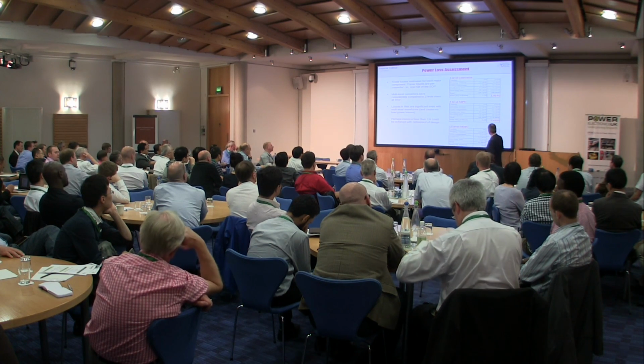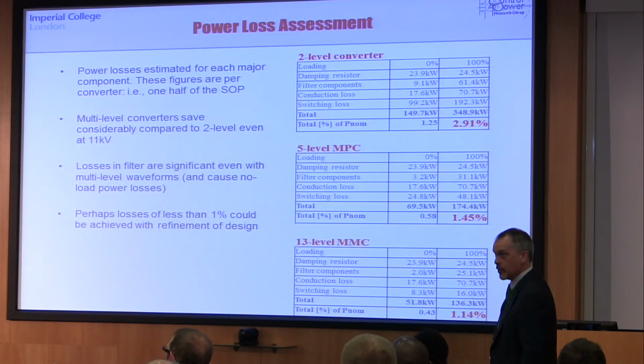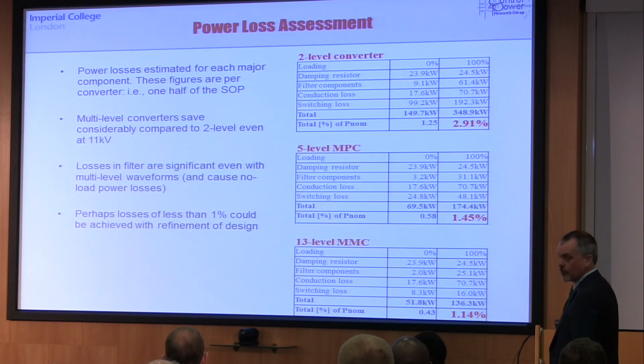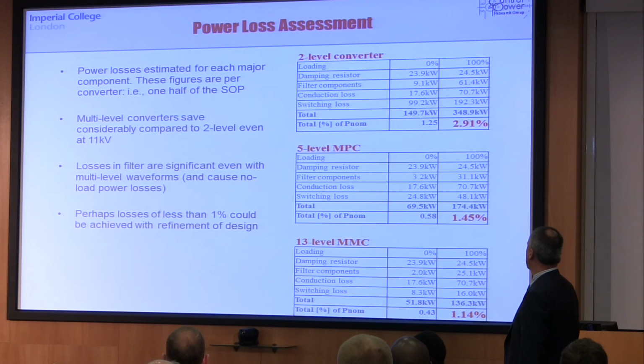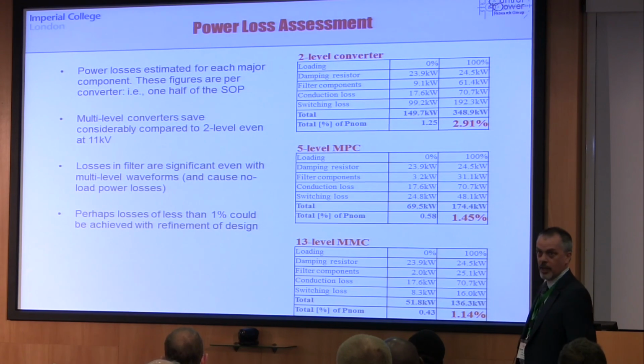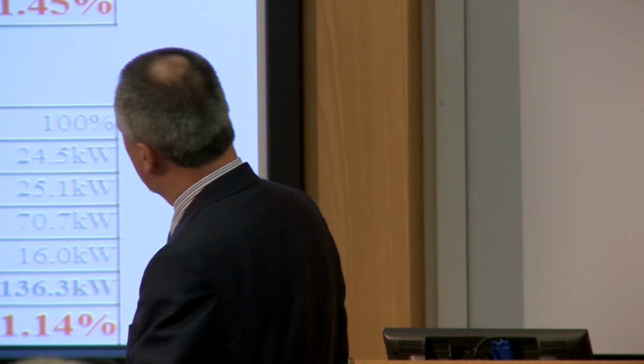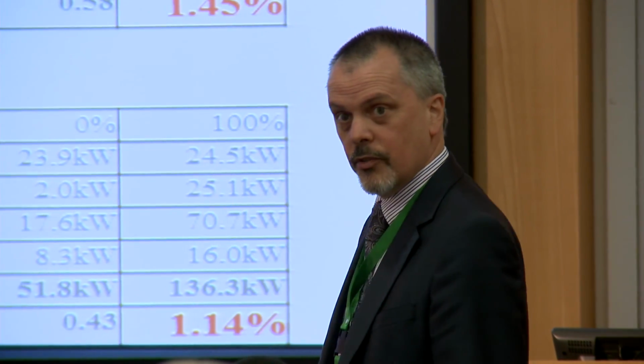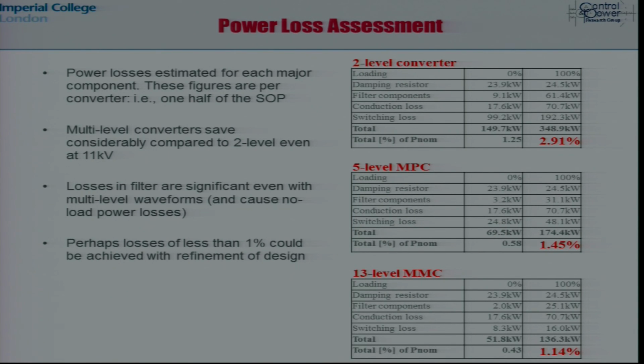In terms of losses, and this is probably where the numbers would get better if we redid the study, going from almost 3% losses in the 2-level converter, because you have to double this for a back-to-back arrangement, down to just over 1% for the MMC version, which is about where we might want to be. But one of the things we found was that the no-load losses are quite significant. You try to run with zero power transfer, but you're still supporting the currents in the filters, and that gives rise to quite considerable losses, even when notionally running at no power transfer.